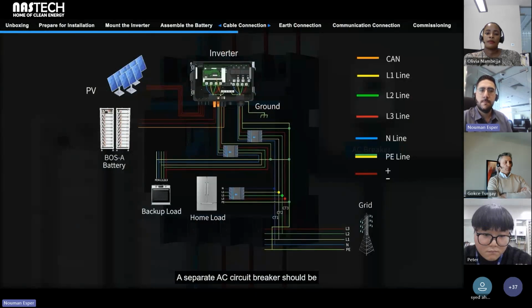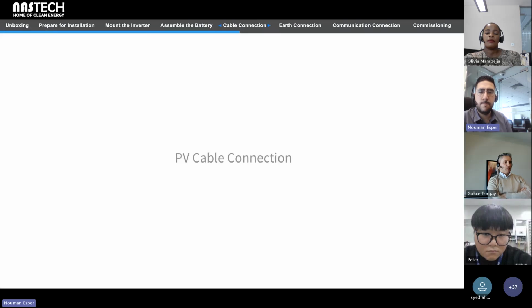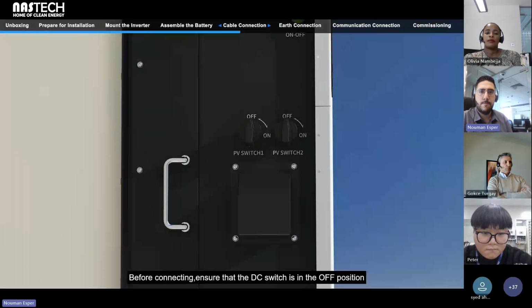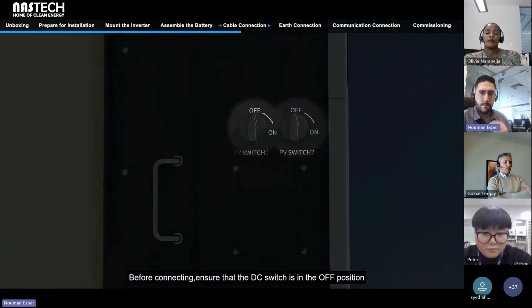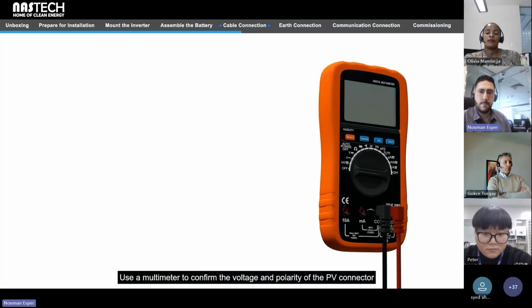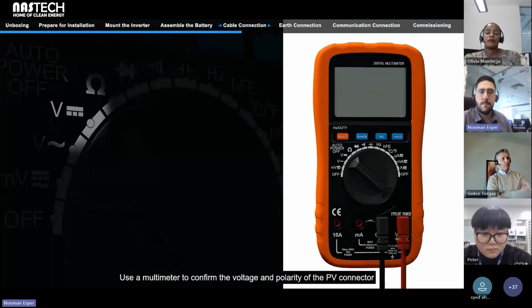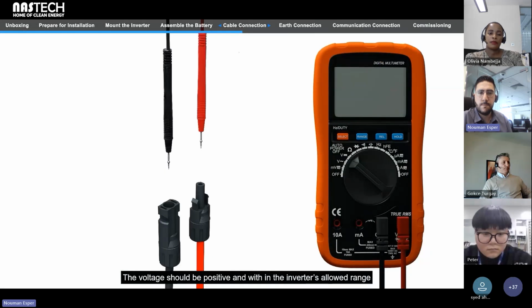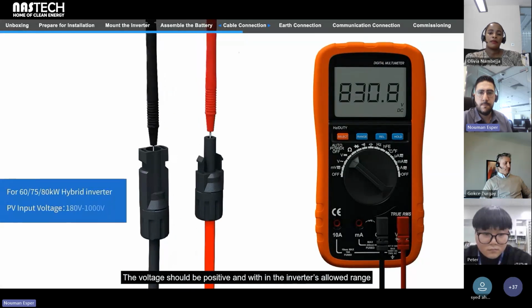A separate AC circuit breaker should be installed between the inverter and the grid. It is also recommended to install an AC circuit breaker between the load or diesel generator and the inverter. PV cable connection. Before connecting, ensure that the DC switch is in the OFF position. Use a multimeter to confirm the voltage and polarity of the PV connector. The voltage should be positive and within the inverter's allowed range.